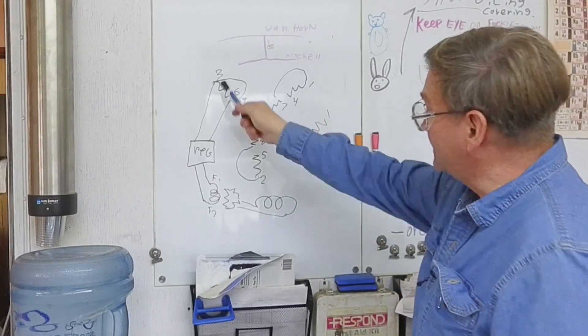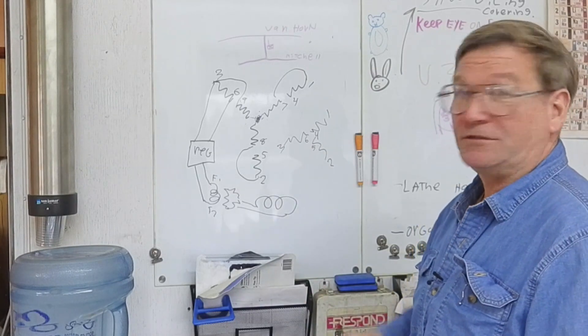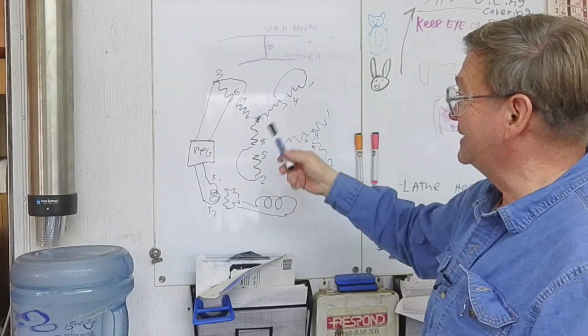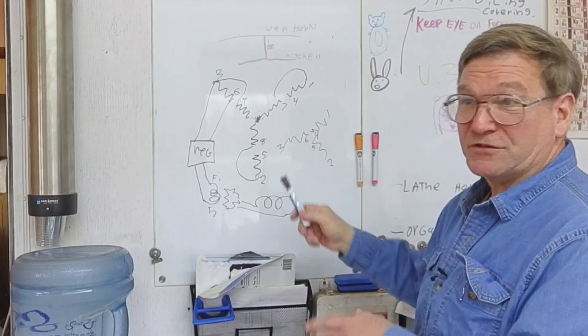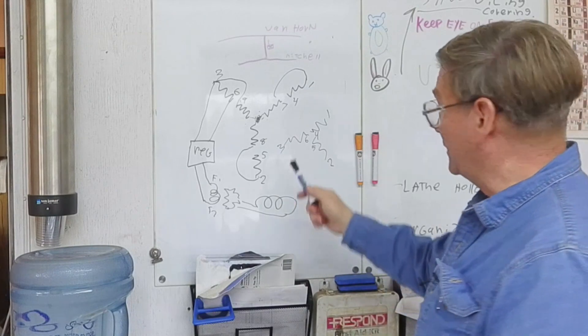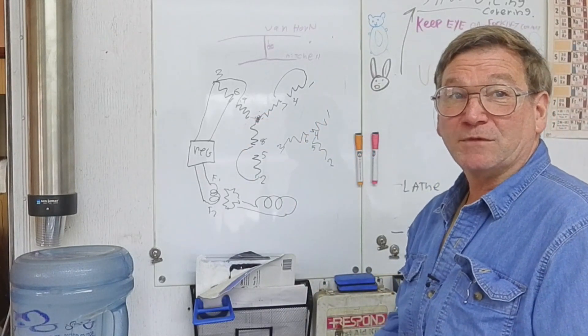And you can actually take a wire. When you understand this, it makes it easier if you're really into stuff. Say you have a motor that's 480 volt only, you come in, start clipping the windings, interconnections, and you can rewire them, which don't just rewire them to be a 208, but come in and rewire them so that you have the correct numbers on the terminals. So somebody later on can change them both ways.